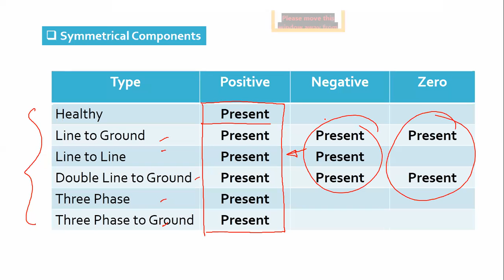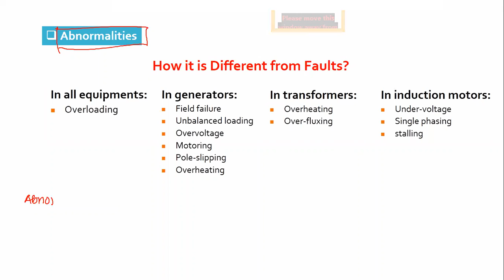Now, the next terminology. We have seen about the fault, its effects, its causes, and everything about the need of protection. The second terminology is called abnormality. So what is abnormality? Abnormal operating condition, or abnormality, can be defined as an operating condition which is not a fault, but if it remains for a longer period of time, then it may result into fault. So it is a situation which is not a fault initially, but if it is there in the system for a longer period of time, it may result into fault.